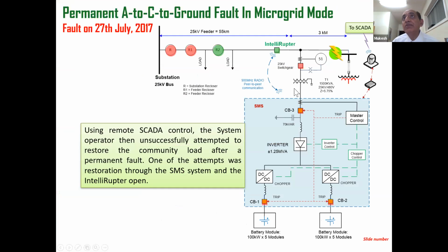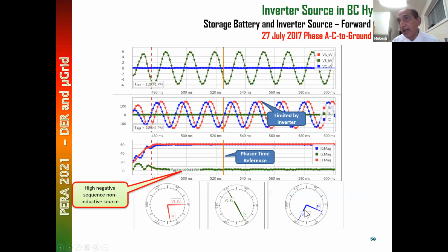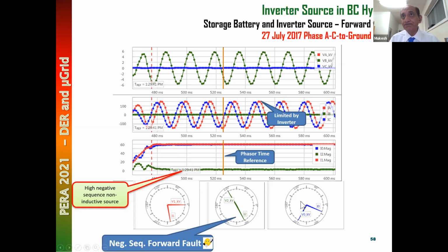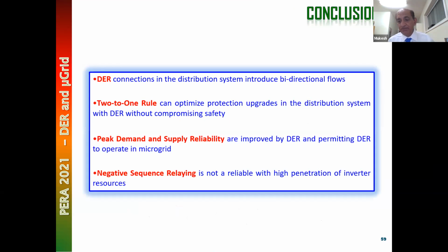So this device cannot make a directionality decision for unbalanced phase faults, the faults which are not involving ground. It can make a decision for ground faults because the ground current is coming from a delta. Look at this, ground current is coming from a delta and it has a 90-degree angle. For ground faults, it makes a good decision. For a phase fault, it has to rely on negative sequence. It cannot make a good decision because the negative sequence characteristic is not like a conventional source. It depends on the grid inverter control system. Therefore, it can only detect the direction of a ground fault correctly, not a phase fault. So the negative sequence element cannot detect, and the zero sequence direction element can work because of the transformer. So these are the conclusions of my presentation.